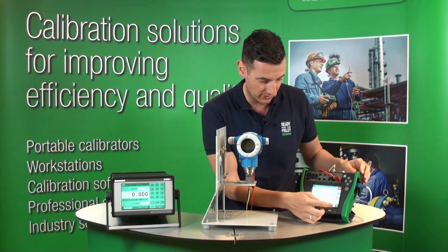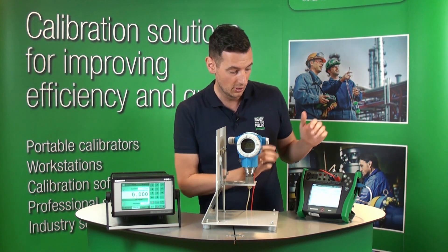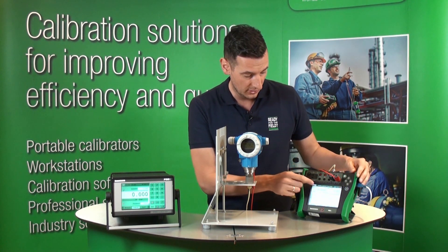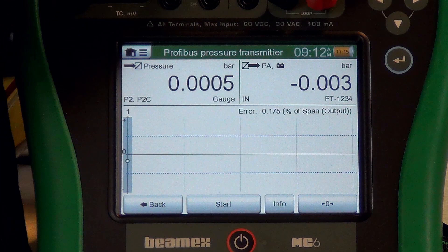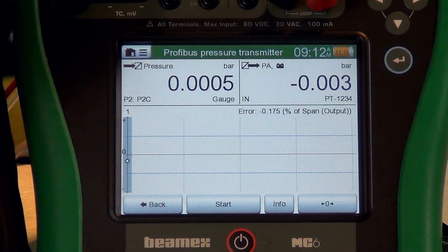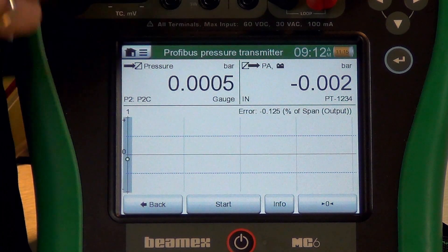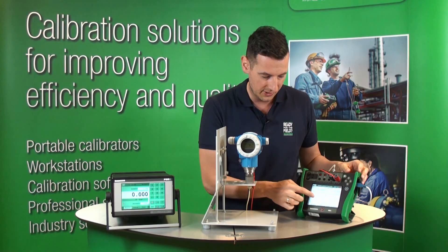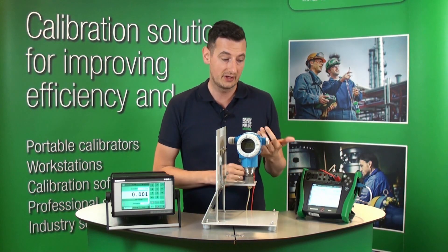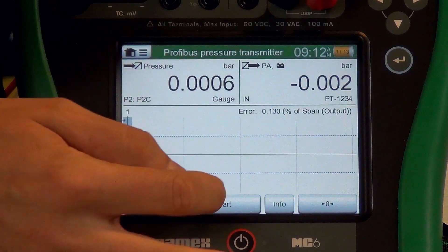We've got everything connected, so we're ready to hit start and go to the calibration screen. On the calibration screen, the top left corner shows the pressure directly controlled from the MC6 and shared between the pressure transmitter and the MC6. On the top right corner you can see the Profibus direct information from this pressure transmitter. You can also see the error graphic limits — those blue lines are the error limits.